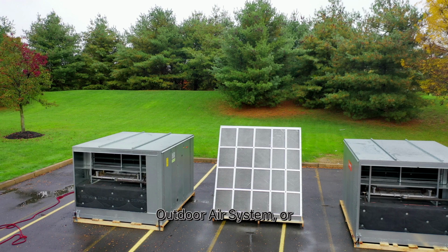Dedicated Outdoor Air System, or DOAS. A DOAS uses a refrigeration cycle combined with reheat to deliver what we call neutral air, typically around 70 to 75 degrees Fahrenheit dry bulb and 50 to 55% relative humidity. This system removes a large amount of moisture before the air ever reaches the occupied zones. Because the outdoor air is already conditioned, the WSHP units in each zone only need to handle the sensible load, meaning they can often be smaller and more efficient. DOAS units are especially common in schools, offices, and hotels, where humidity control and comfort are top priorities.